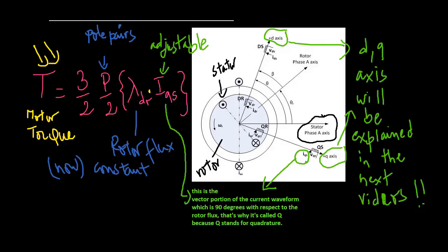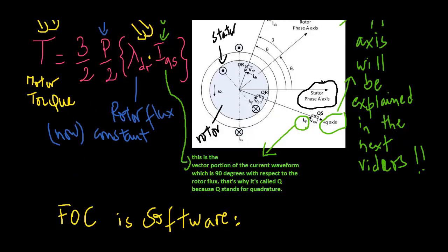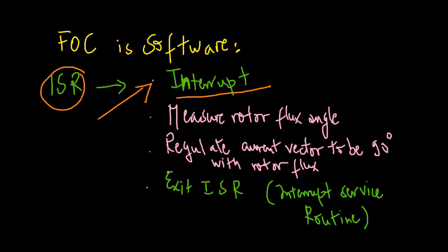In the next video we will show that the torque is calculated with a specific expression. The component IQ is the current component that controls the motor torque. To do field oriented control on a digital processor, we get an interrupt service routine, go out and measure the rotor flux angle using sensor or sensorless techniques, then regulate the current vector to be at 90 degrees with respect to the rotor flux by adjusting the three stator phase currents. This is done approximately 10,000 times a second — every 100 microseconds we check the new angle of the rotor flux, recalculate the three currents to be exactly in quadrature, and then exit the interrupt service routine.